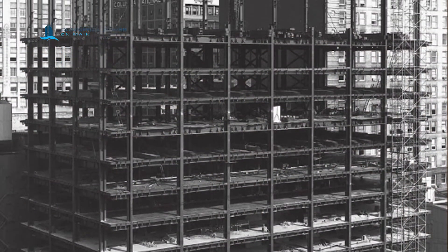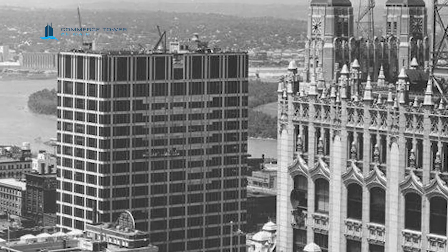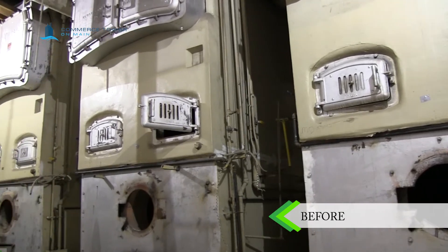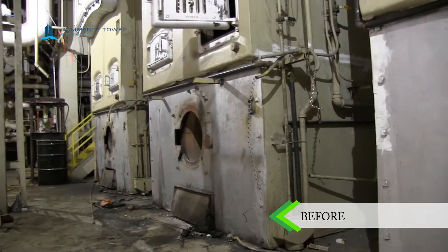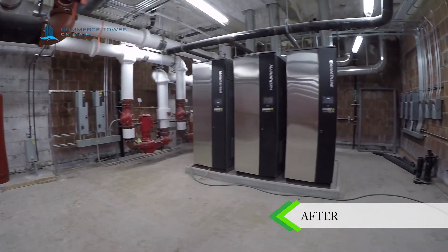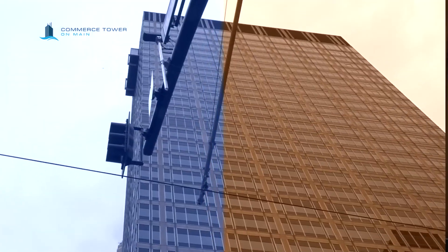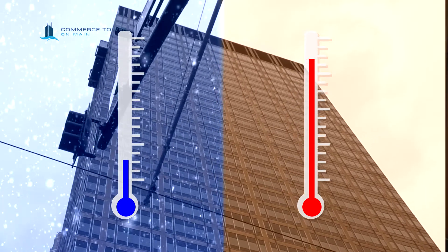It was built in 1964. At the time it was cutting-edge technology, but we find ourselves 50 years down the road with bigger, better, and more efficient systems. This used to be run by a steam chiller, and the building was fed by three independent boilers that looked like three number-seven locomotives. Those boilers were very ineffective and outdated, so they've been demoed and removed. We're coming back in with high-efficiency natural gas-fired boilers. The building was a two-pipe system, which means if one person at one end is hot, the other end is freezing — nobody's ever happy and you get a lot of phone calls.